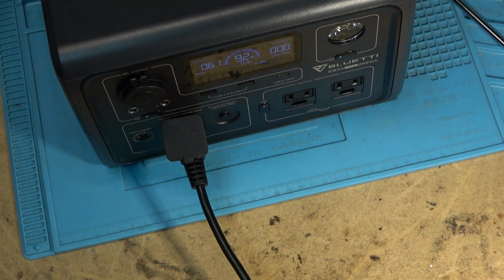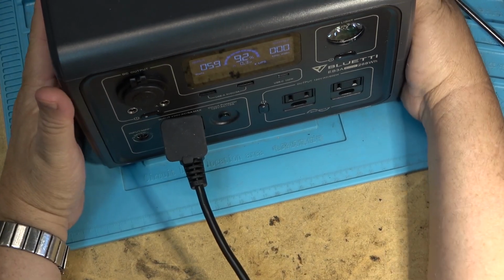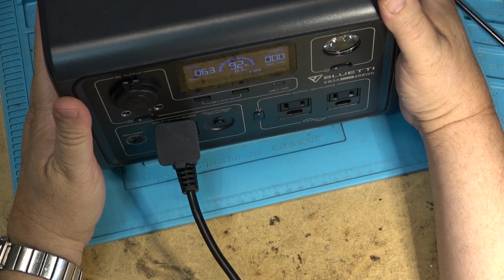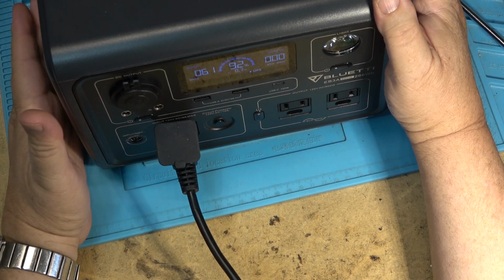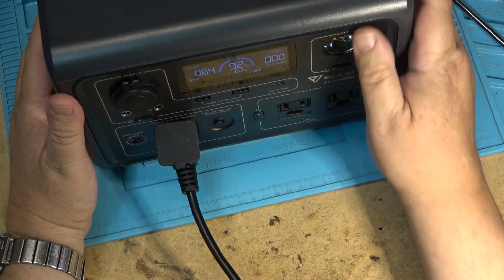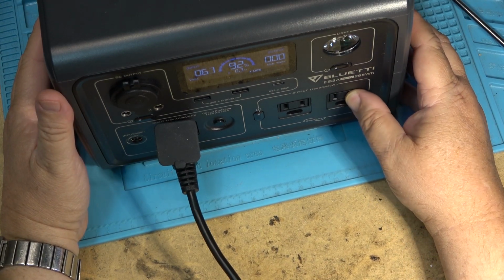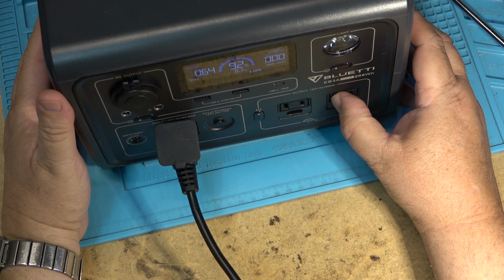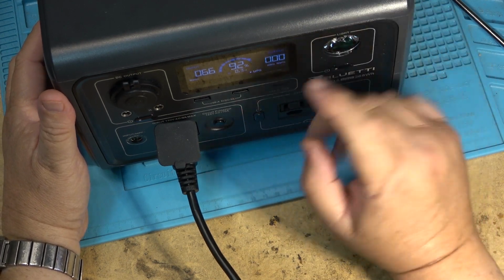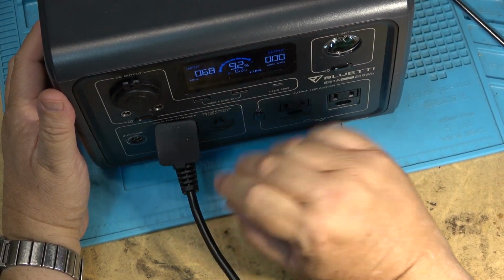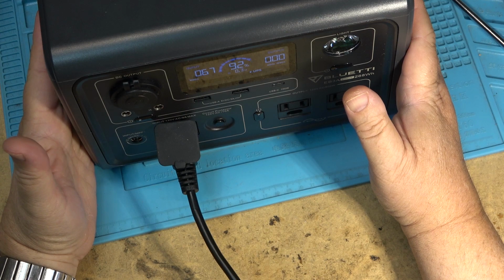So eco mode could be left on if you were using this as a UPS to power a computer, for example - a computer is going to draw more than 10 watts, so it won't shut down. But if you were running something of very low power, like some LED lights drawing less than 10 watts, and you didn't want them to shut off after 4 hours, you could turn eco mode off, and then the unit will stay running until the battery is depleted.